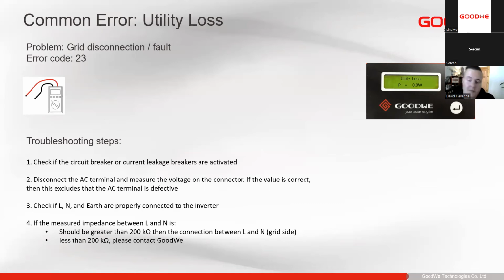Sometimes it could be that one of the circuit breakers might have tripped. So if we undersize our circuit breakers or size them just on the level, when the circuit breaker is warm, they degrade as well, and then those circuit breakers tend to trip. And it is not good for the system for a circuit breaker to trip under load. It should only trip when there is a cable fault.